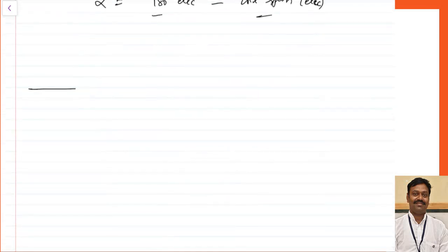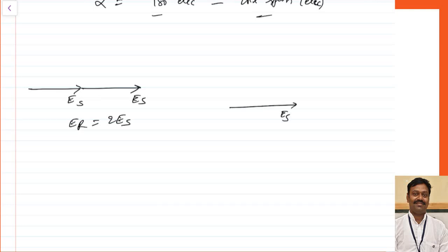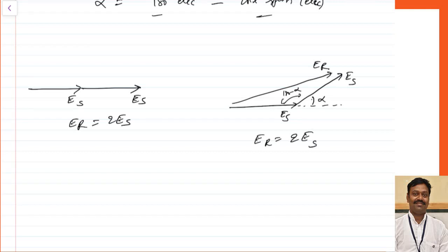Let us see the difference between full pitch and short pitch. In a full pitched coil, if the EMF induced in each conductor is Es, the total EMF equals 2·Es. Whereas in a short pitched coil, instead of Es being in direct opposition, because you are short pitching by angle alpha, the EMF will be shifted by that same angle. Your resultant EMF will be equal to 180 degrees minus alpha. The resultant value of EMF becomes 2·Es·cos(α/2).